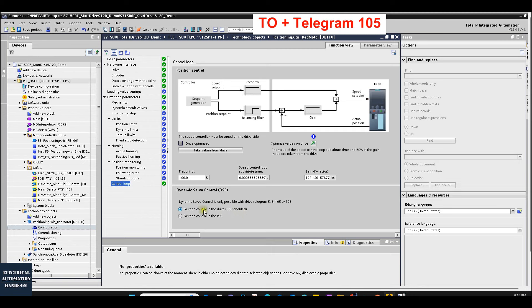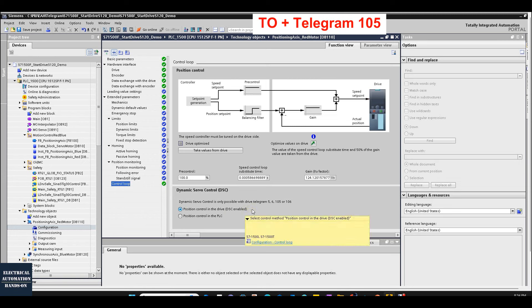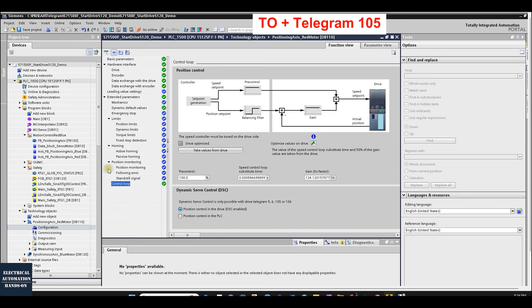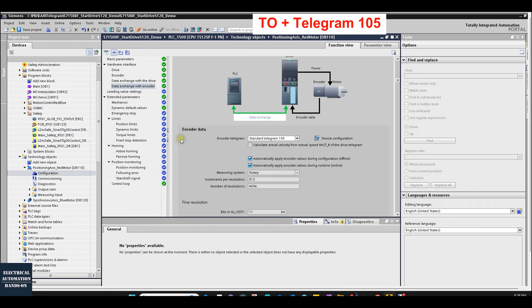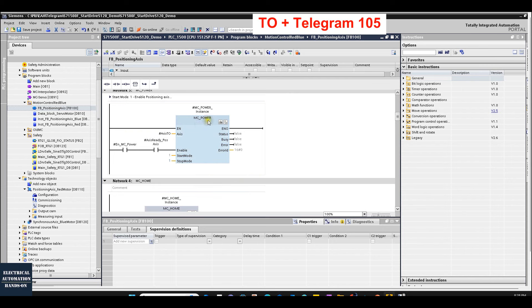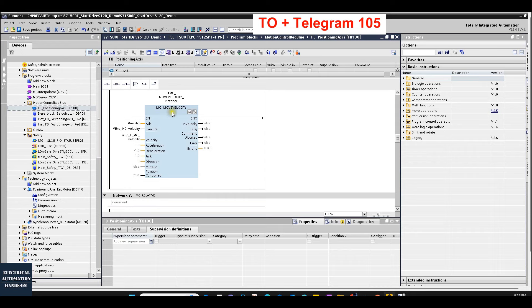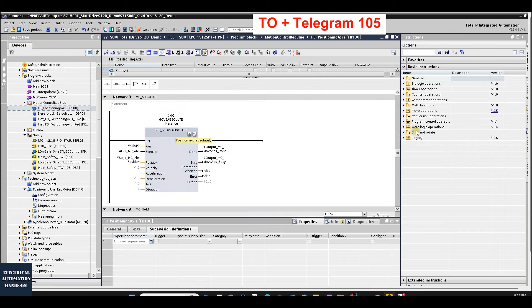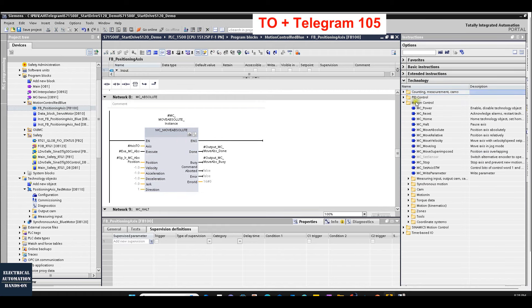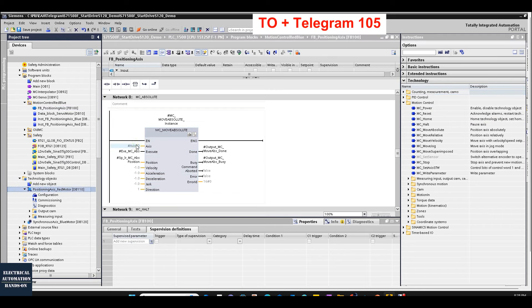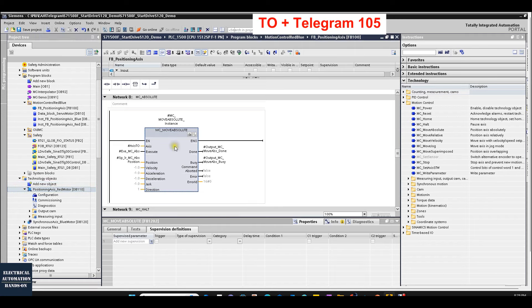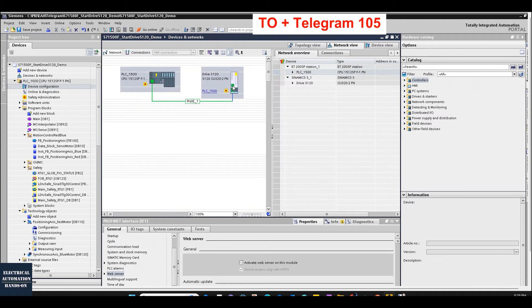From the encoder, in some cases you need the X_IST bits — these all automatically configure. Under the control loop option you will see DSC — Dynamic Servo Control — default selected as 'position control in the drive.' Don't worry, Siemens defaults this DSC enabled. This is the typical telegram 105 for positioning control. Then when we shift to programming, you can use IEC standard motion control commands: MC_Power, MC_Home, MC_Jog, velocity control, MoveRelative, and MoveAbsolute. All these standard motion control commands work with the TO, and this function block controls the servo drive.